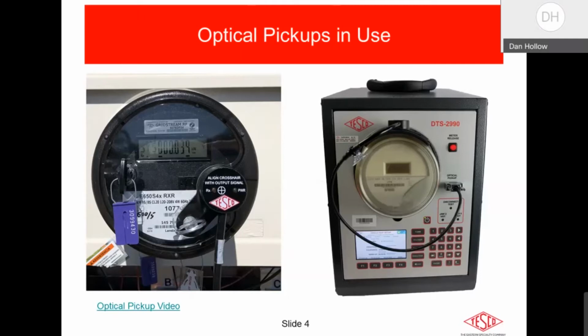The infrared LED that's putting out the infrared test pulses can be in various locations. Some come right out of the optical port itself on the front of the meter. Some come out on the top, like you see this one here on the right. That one has it at the 12 o'clock position. This particular configuration is somewhat problematic, so we've created a product that allows it to hold it in place where that infrared LED is on this particular meter and be able to pick up that pulse uninterrupted. And some of the meters will have them coming out at the 9 o'clock position, some at the 3 o'clock position on the face of the meter.